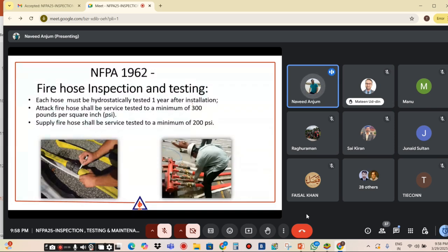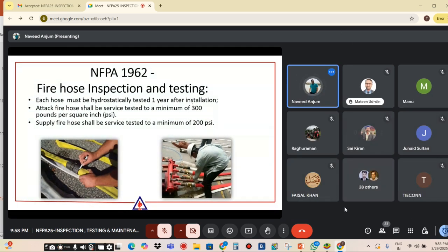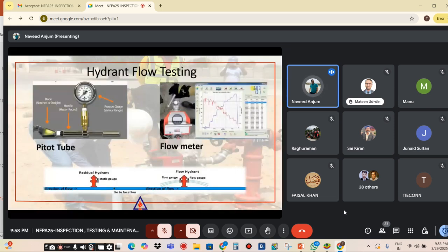Because we are discussing water-based systems, I have also added some hoses, because in my different visits I have seen that mostly no one is testing the hose system. It is also required as per NFPA 1962 for fire hose inspection and testing. Each hose must be hydrostatically tested every year after installation. If we have attack hoses, then we have to test at 300 psi, and if we have only supply hoses, then we have to test at 200 psi. So this is also mandatory.